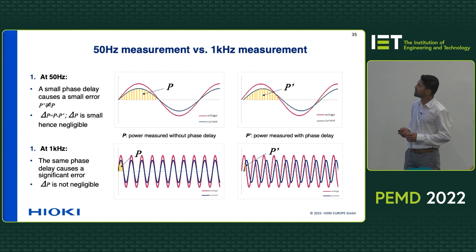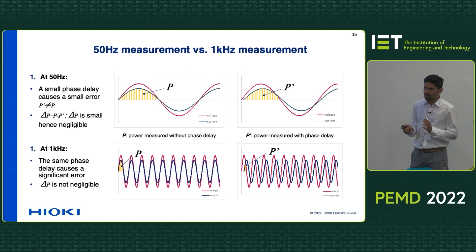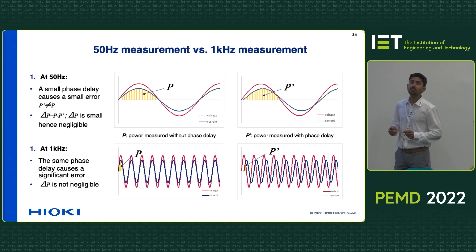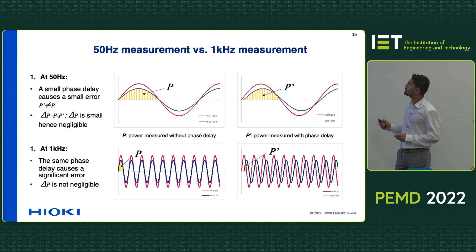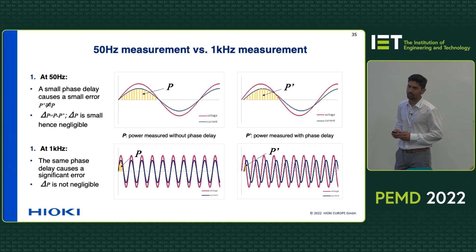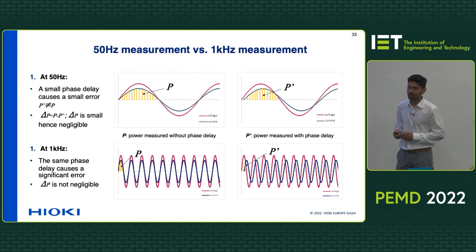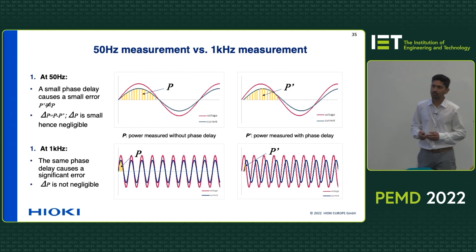The power that we are going to measure is not going to be the same — it's going to be a little bit different. The power we are measuring is P-dash, which is not exactly the same as P, but there is not a big difference. But if we do the same thing at one kilohertz of frequency, the same amount of phase error will cause a big difference in the power that we are measuring. At frequencies higher than one kilohertz — say 10 kilohertz or 100 kilohertz — this error is even more prominent.